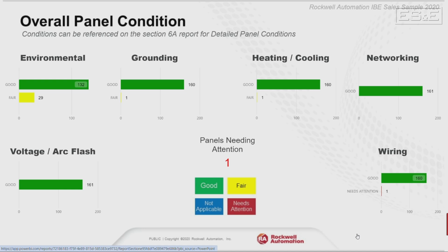Like I said, we mark needs attention. So in this particular report, one needed attention. 29 of them had a fair environment. You know, it could have been a little bit dirty around the panel, could have been a little dusty inside the panel, but nothing to where we felt like we needed to make a needs attention note, right? There was only one of those there.